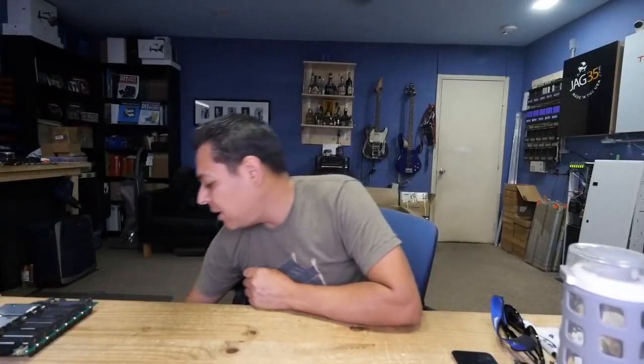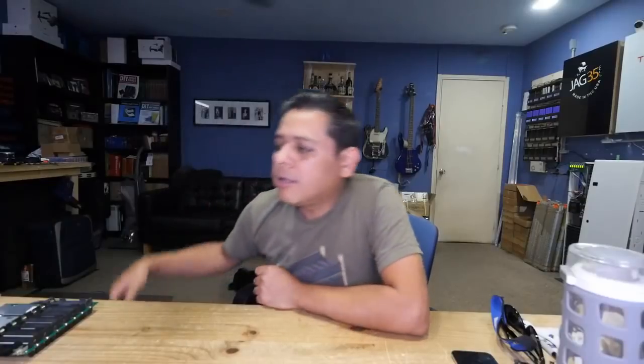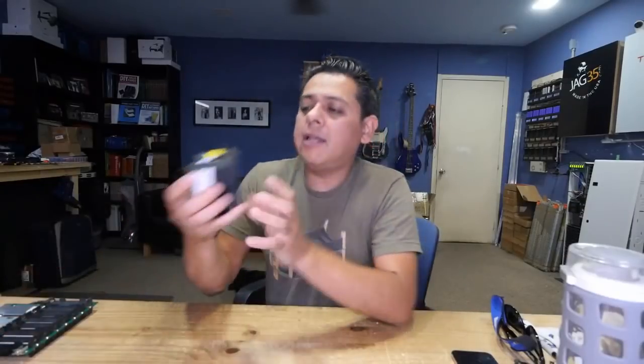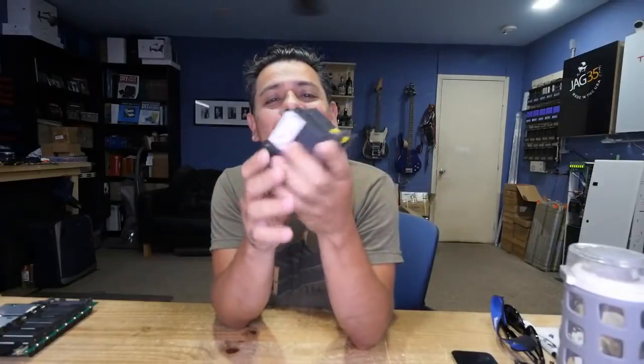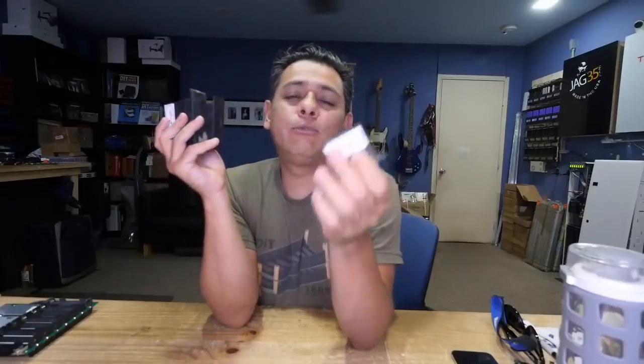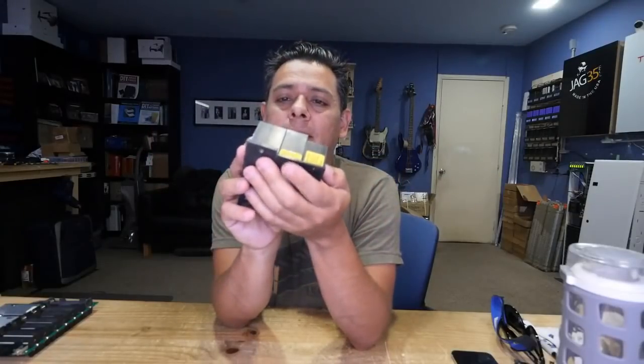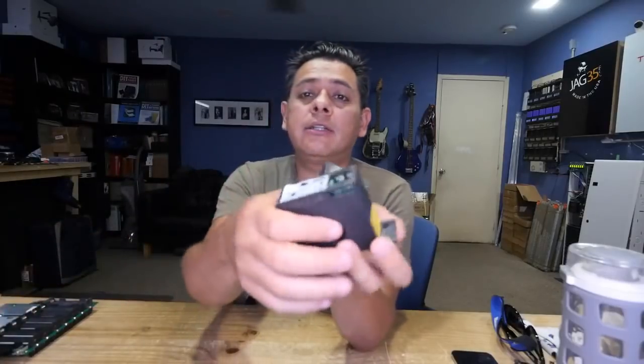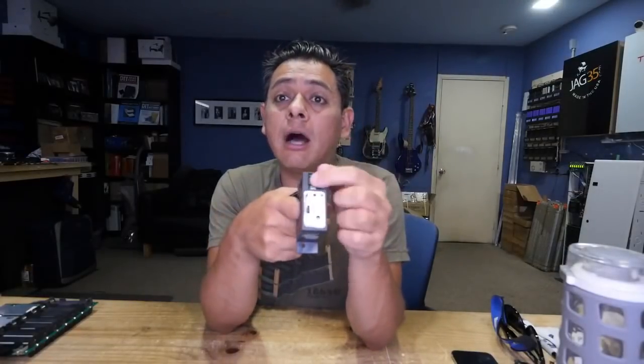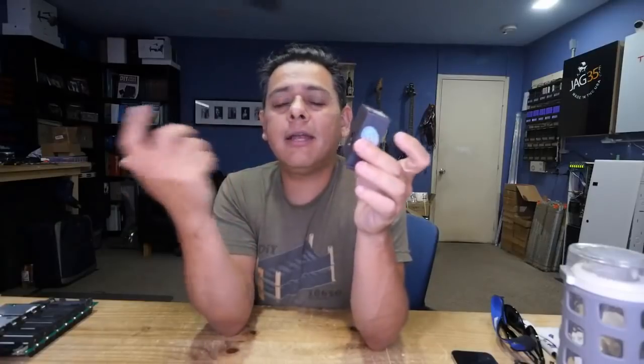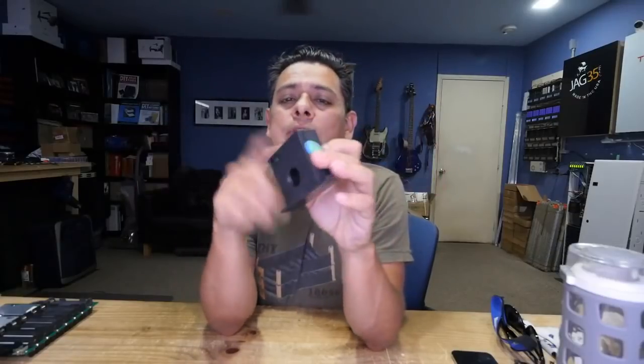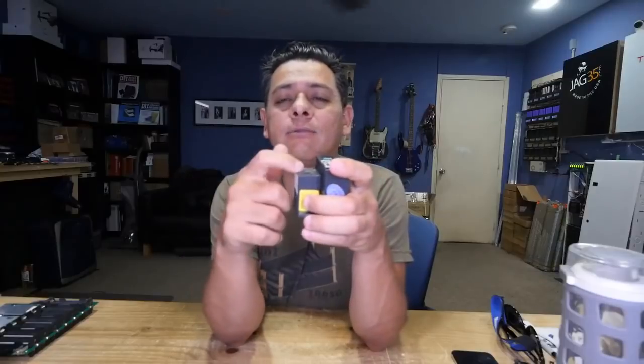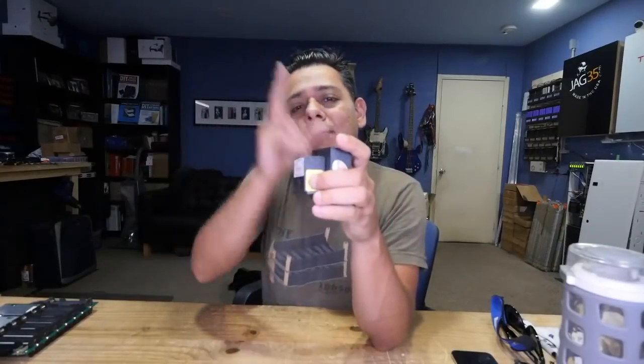As far as limiting it so you don't throw more energy back into the grid than you're using, I'm using a group of these clamp switches. These are all settable, well, actually this one's not, but this one is. You set the amount of amps it sees, and it triggers on and off. So you can set it to turn on after it sees 20 amps, which is about 1,000 watts... actually that's 2,000 watts, so 10 amps. If you set one to 10 amps and put another in line set to 20 amps, then when it sees 10 amps, one of them will turn on.